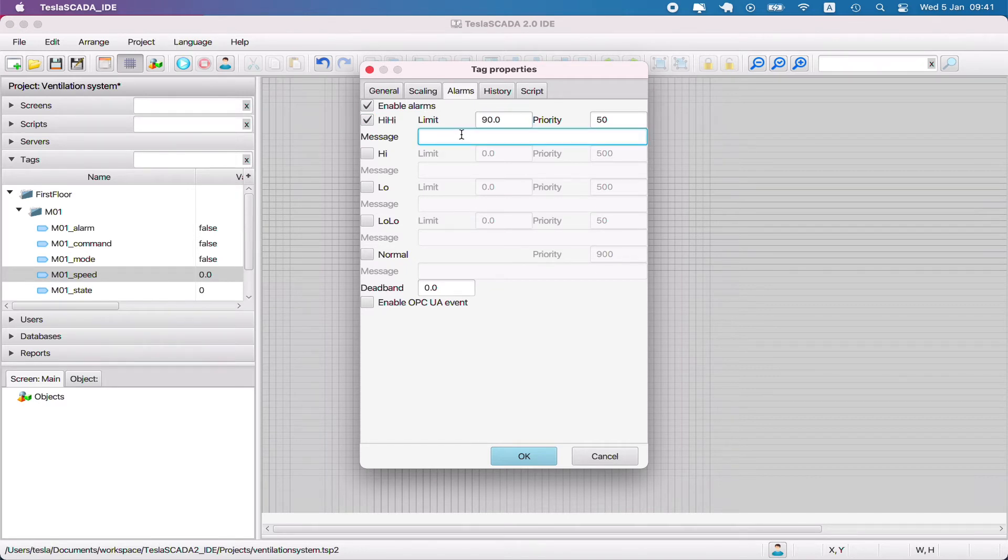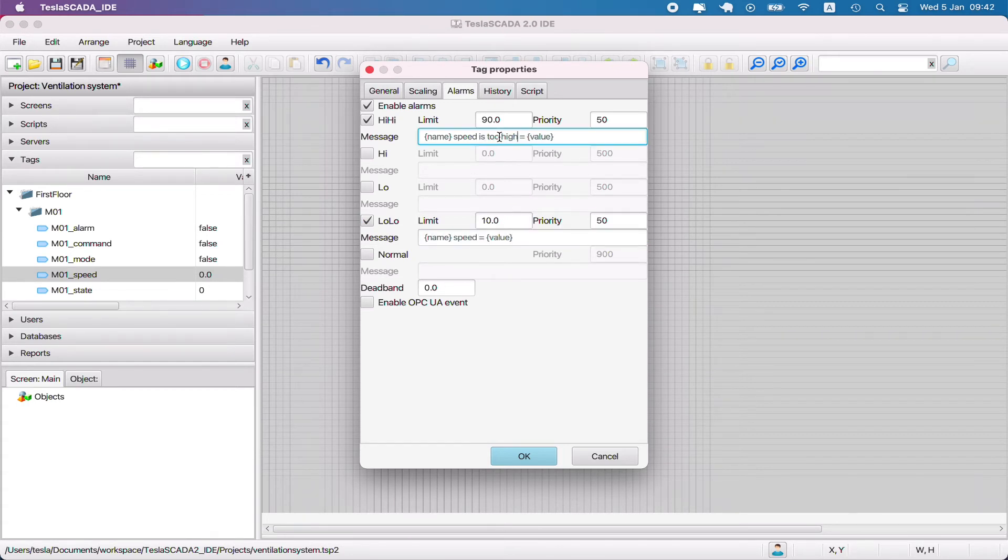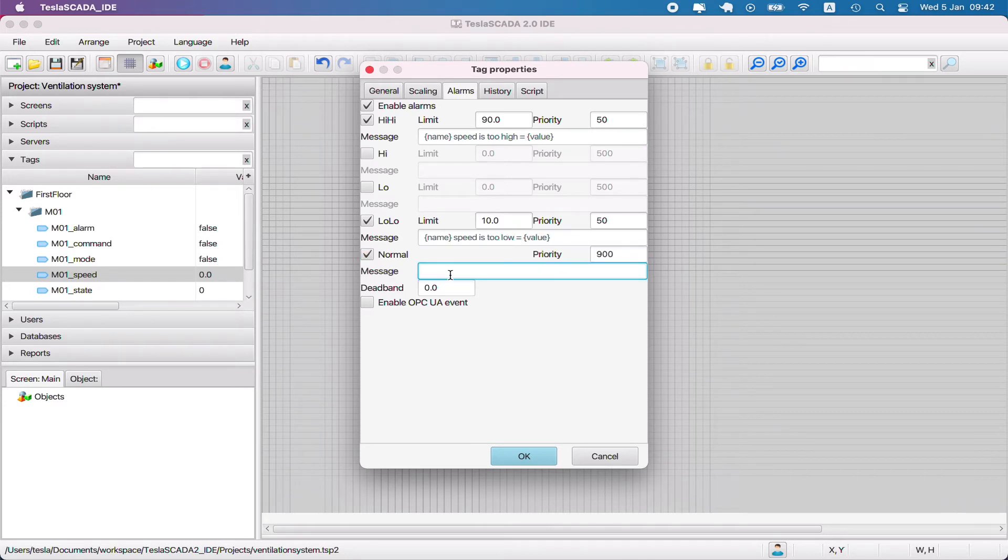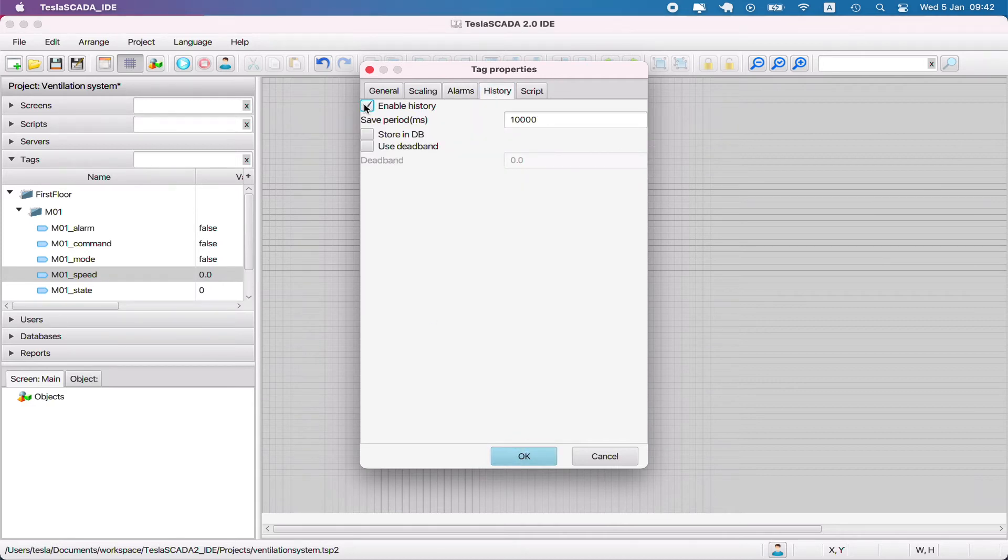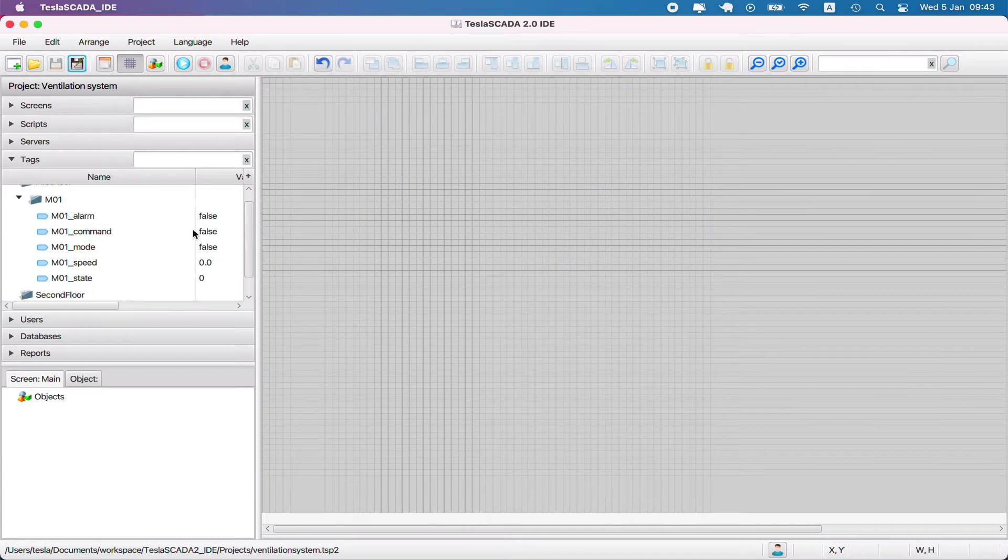Let's set up another alarm for the tag speed. We use the same keyword name and use keyword value to demonstrate current value of this tag. Use priority for alarm high high and low low 50, and for normal message 900. Enable history to collect history information for this tag in database.